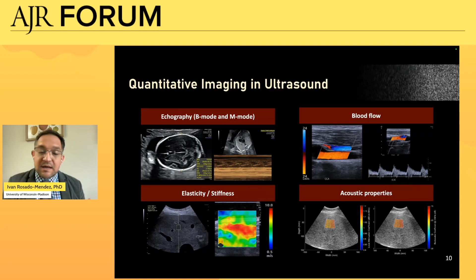The most basic one that you're familiar with is the use of B-mode images and M-mode images to measure distances and motion. This is made possible by the use of short ultrasound pulses that travel along well-defined directional ultrasound beams, like the picture or animation that I showed a few slides ago. This allows for a correct spatial localization of echo sources, what we refer to as echolocation. So we can locate the sources of echoes in two dimensions, for example, in the axial location, that is the direction of the propagation of the wave.